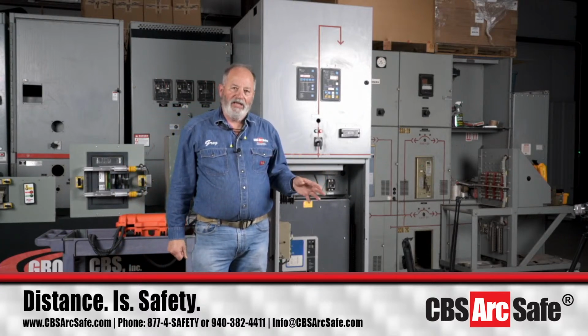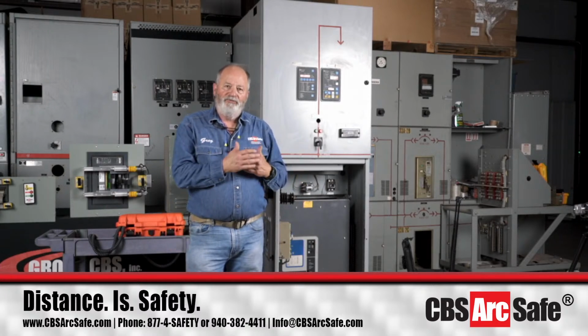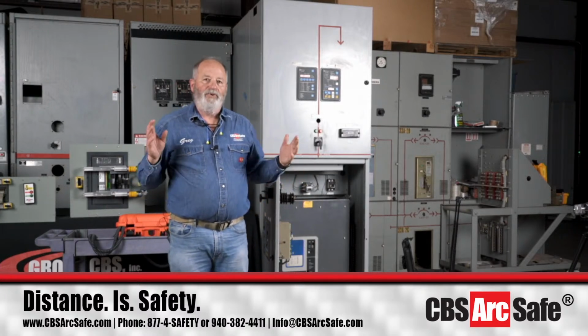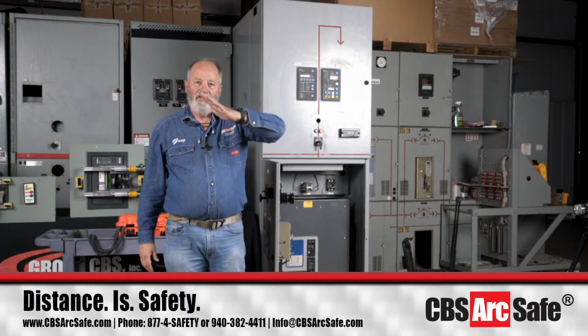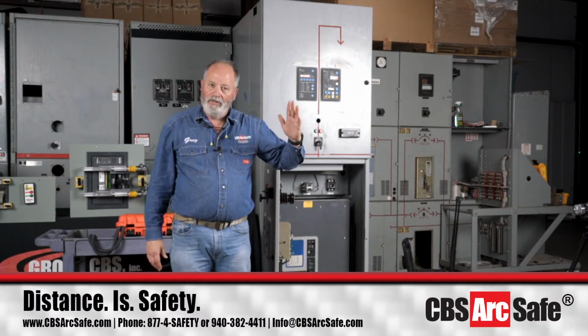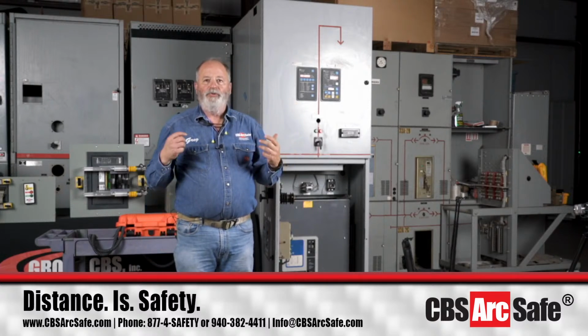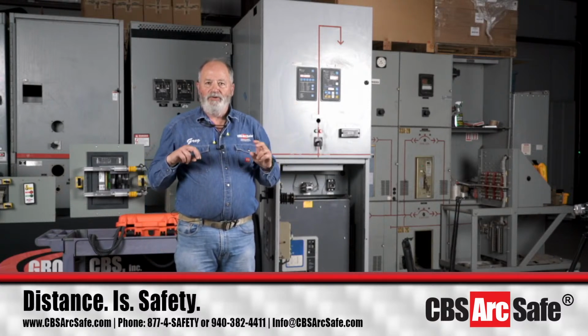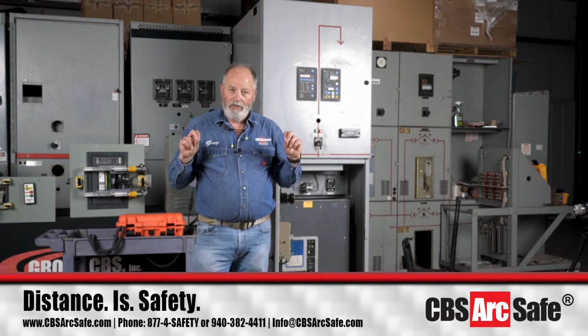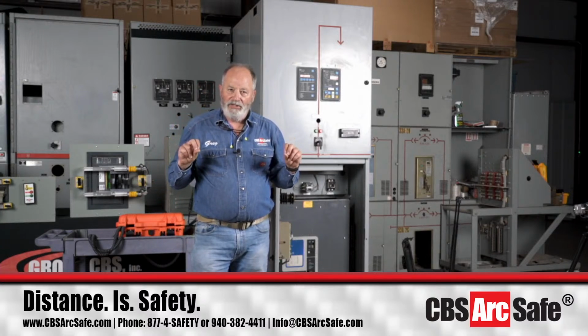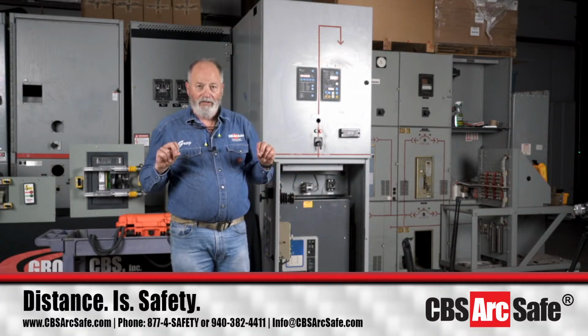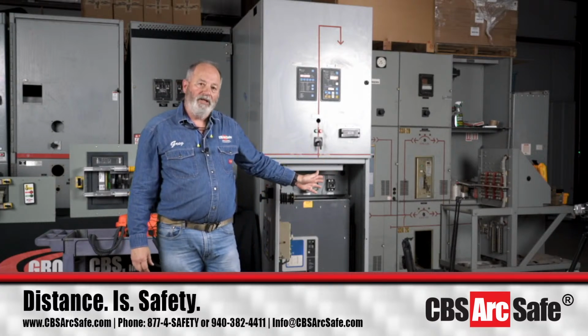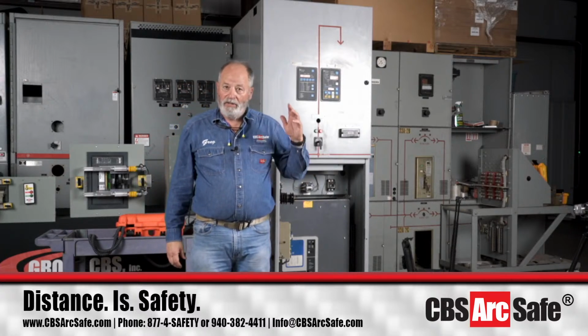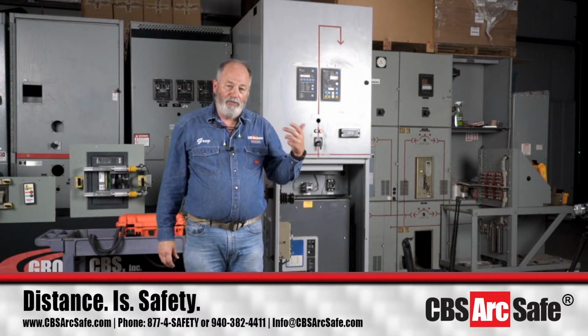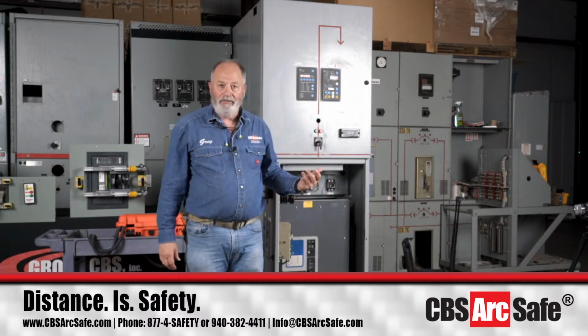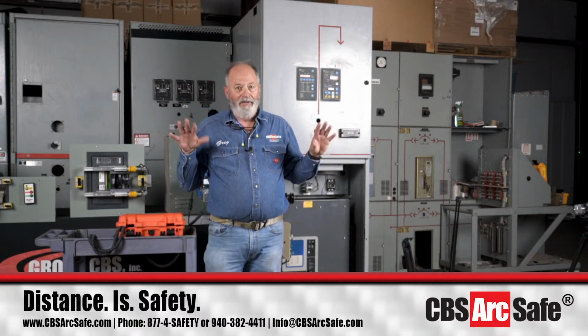I have seen a substation where it was 27 foot-pounds going in and out on every single 3000 amp breaker in this substation, and kick out at the top and then reverse that angle as it came back out. The people who made this said it was made within specs according to Eaton's design specifications, even though the breakers did this. And inside of the power plant where this stuff was, they had the same style breakers, and they only took like 14 foot-pounds to go in and go out on an RS1, but they said, is this normal? And I said, no, not really.